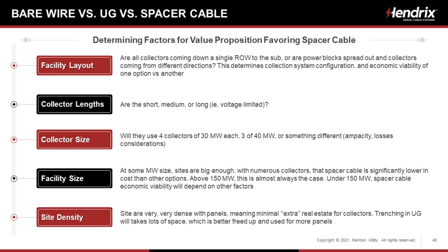Facility size. At some megawatt size, sites are big enough with numerous collectors that spacer cable is significantly lower in cost than other options. We've looked at many dozens, scores of these projects above 150 megawatts, and this is almost always the case that spacer cable would have a value proposition. Under 150 megawatts, I have to take a look at it and compare underground, bare wire, and spacer cable.